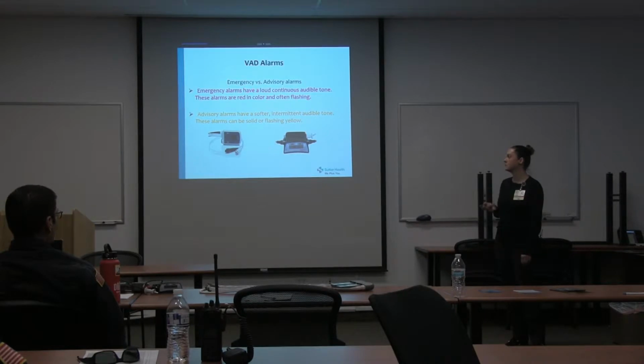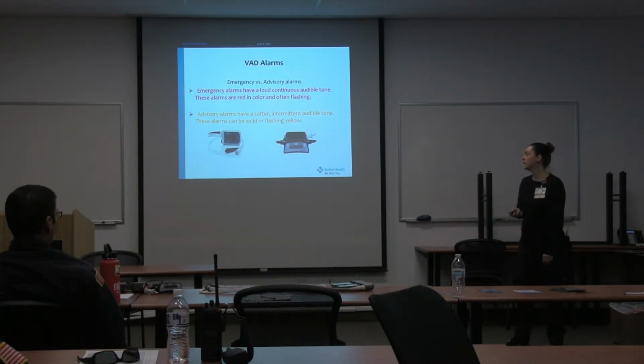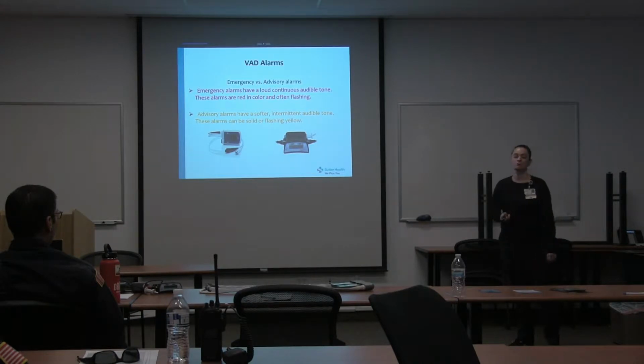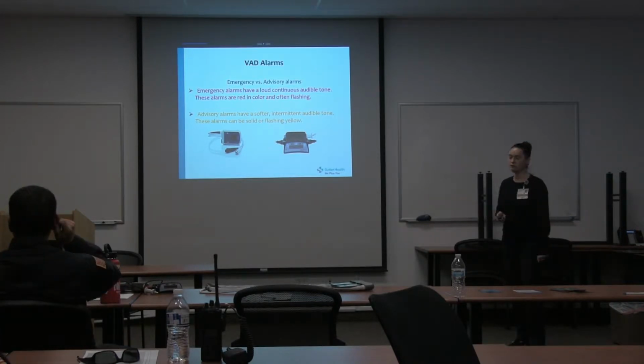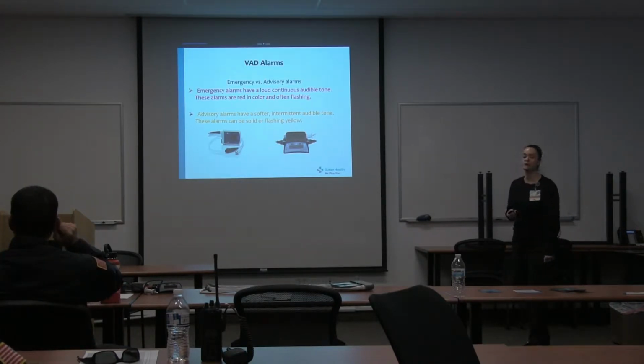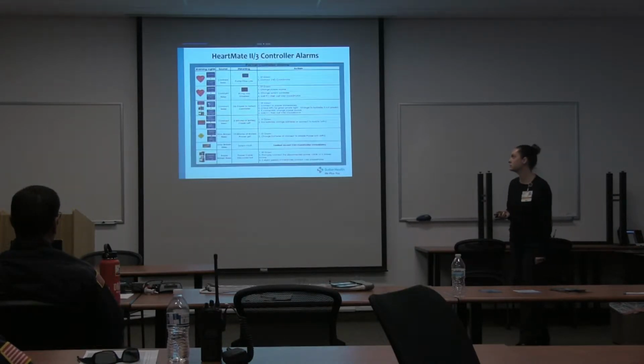They have red alarms that are constant screaming alarms. They're often flashing, sometimes not, but those are your emergent alarms. Those are the stop, we got to fix this right away. Then you have your advisory alarms, which are always yellow, soft broken beeps, sometimes flashing, sometimes not. So that's how all the alarms work, no matter what brand of pump that you're dealing with. Green is good, yellow is slow down, let's talk about it, don't freak out, red, stop, we have a big problem. That's how the alarms work.